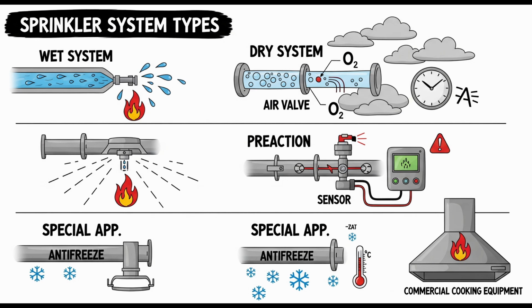So if you already have the extra protection against accidental discharge provided by a double interlock system, or if the pipes are filled with antifreeze, meaning immediate water delivery isn't the only goal upon valve trip, then standard detectors listed for cold environments are acceptable, even if they might not strictly activate before a sprinkler potentially could in a very fast fire. Exactly. The system's inherent design, double interlock needing both detector and sprinkler, or the medium being used, antifreeze already in the pipes, changes the risk profile and modifies the requirements for the detection speed relative to sprinkler activation. Interesting interaction between system type and detector requirements.